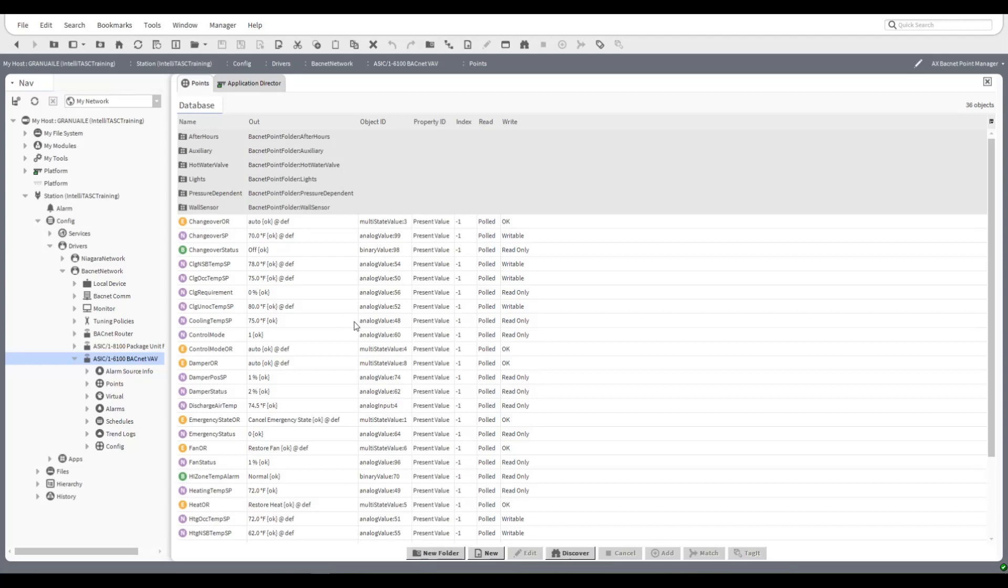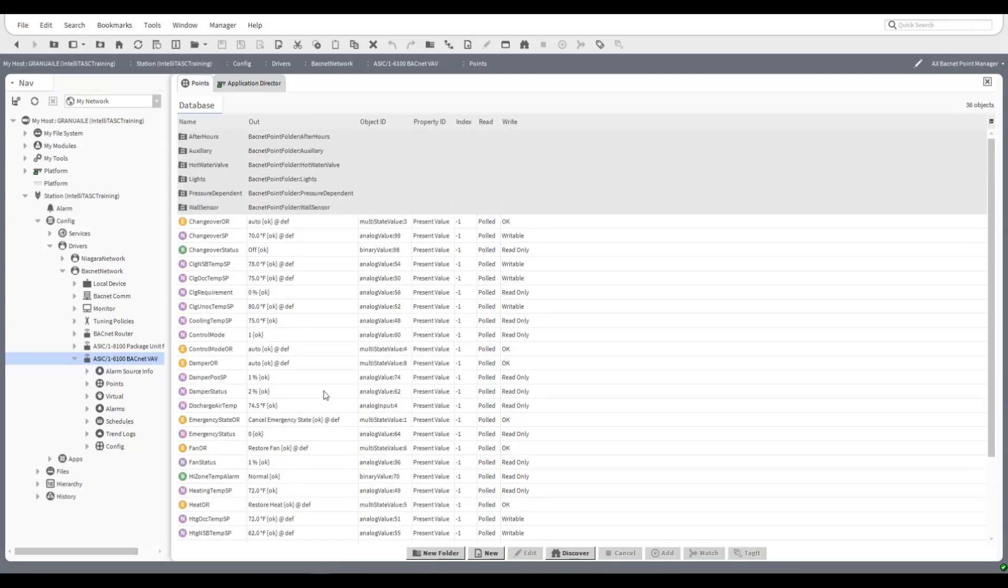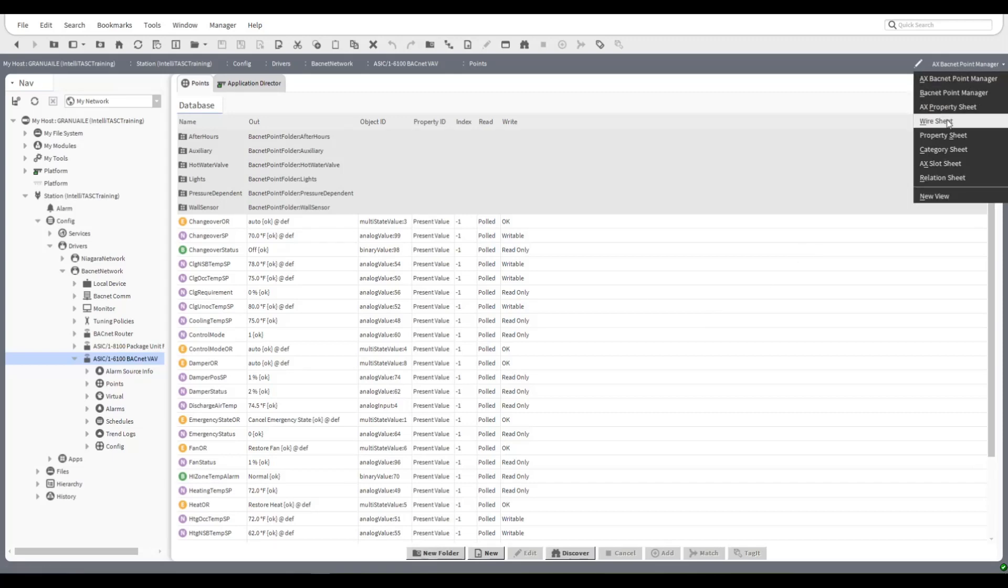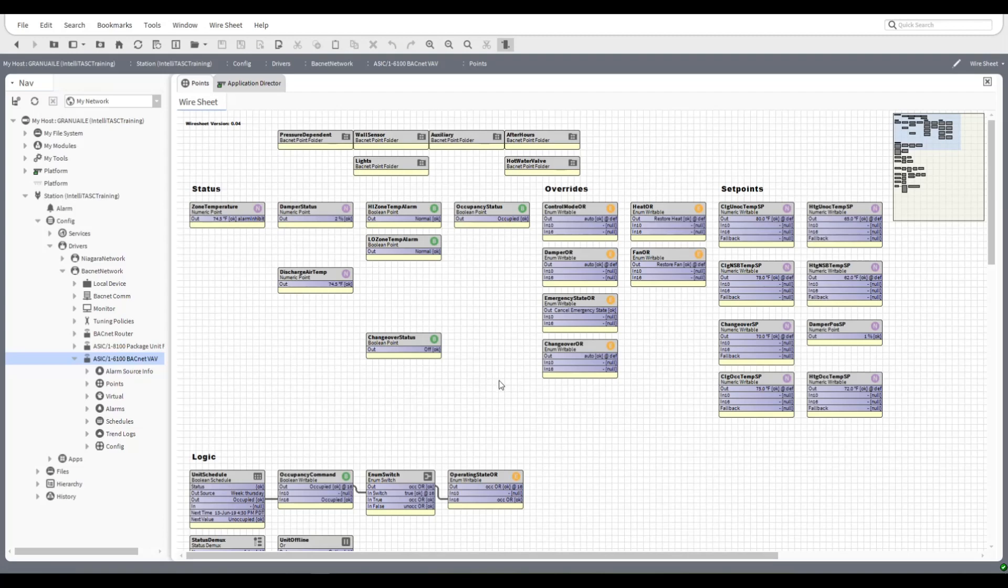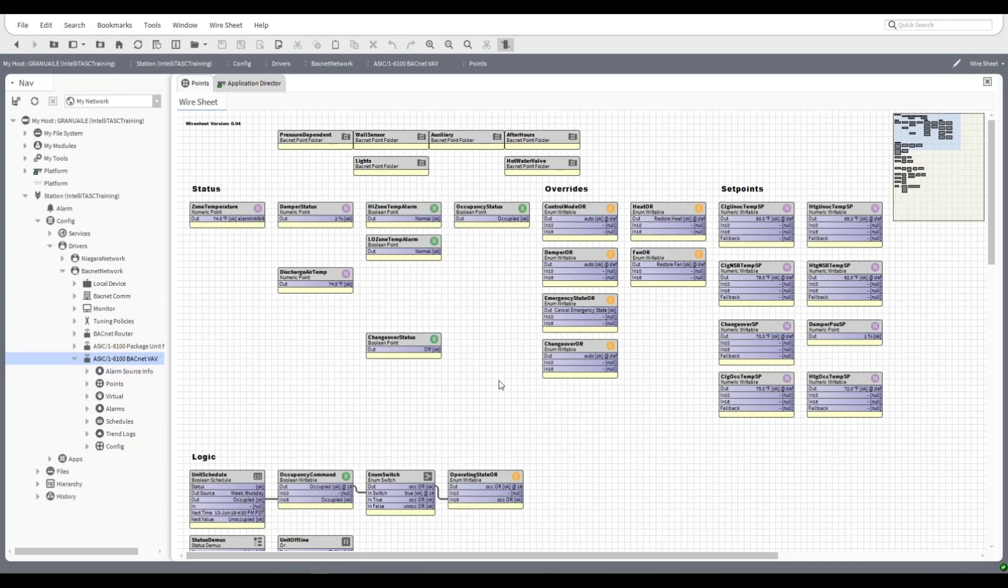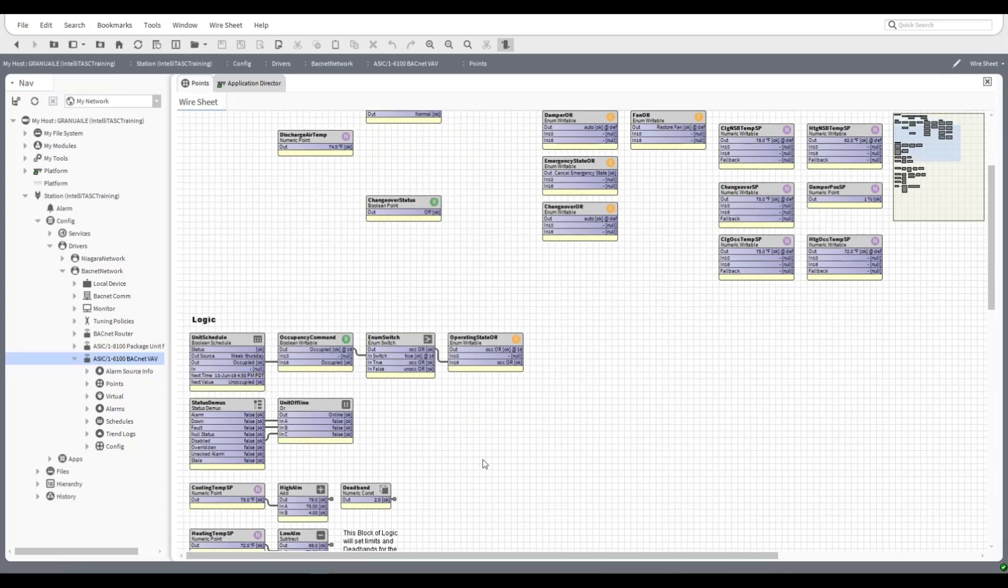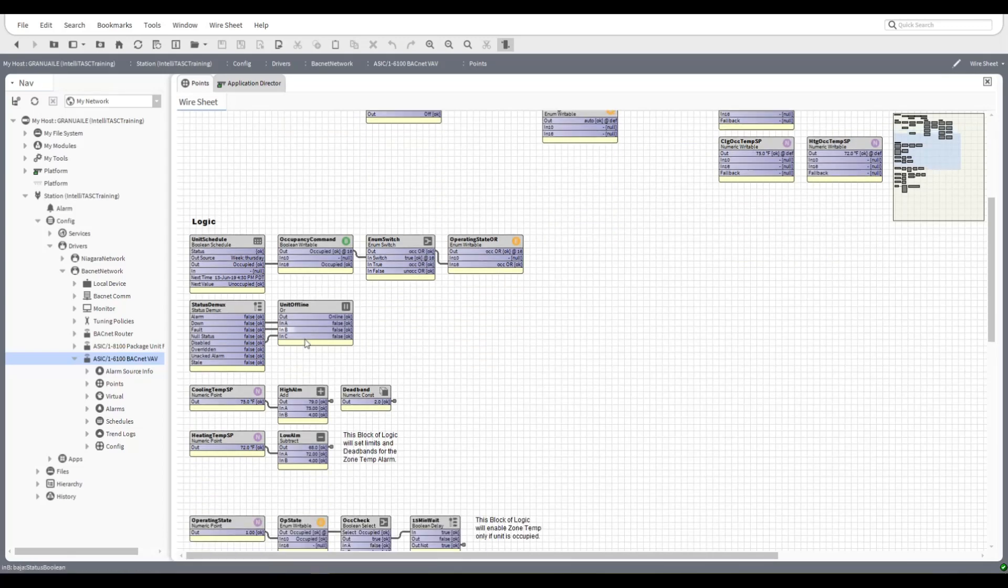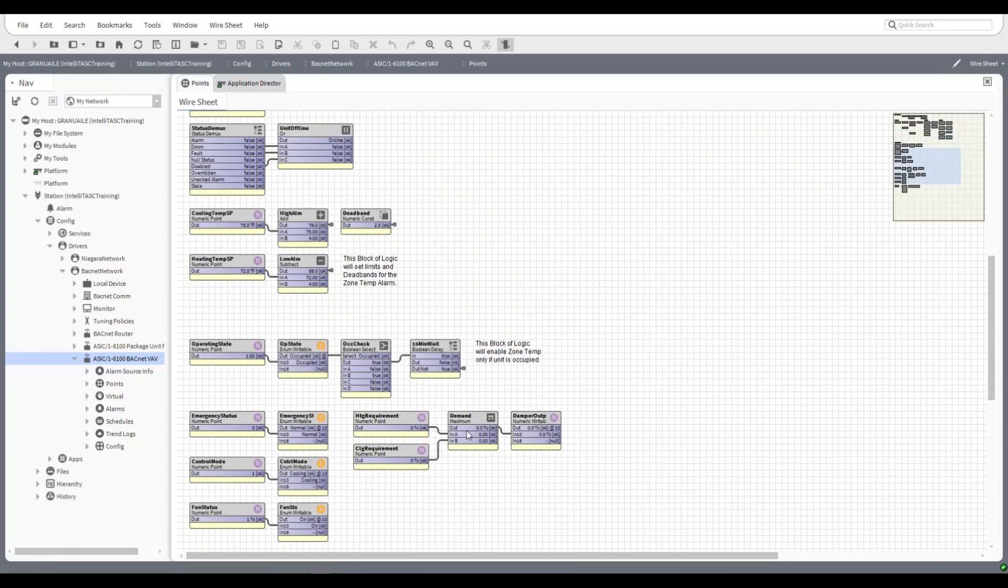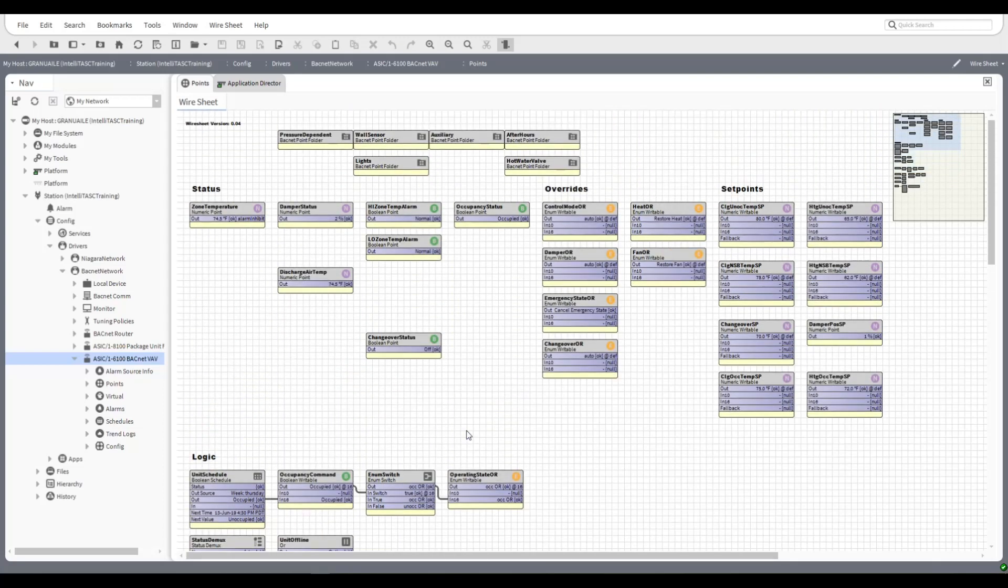Now this current device is a personality 12 device, VAV, so it's going to have the points that we only need for personality 12 and that's what's nice about bringing it in with the services. Because we're using the service, the service actually intelligently goes out to the device, has a look to see what has been configured on that device, and will only bring in the points that are relevant for that configuration including the personality. Let's have a look at the wire sheet view. You will automatically get a nice neat wire sheet that's been put up for you. You're seeing gaps here because there are points that are not being brought in because this personality doesn't need those points, but it's bringing in the relevant points and you can see there's a lot of stuff that's already pre-modeled for you in terms of logic. You have a good start with the configuration without having to have done anything, just one click of the button and you're getting all of this data.